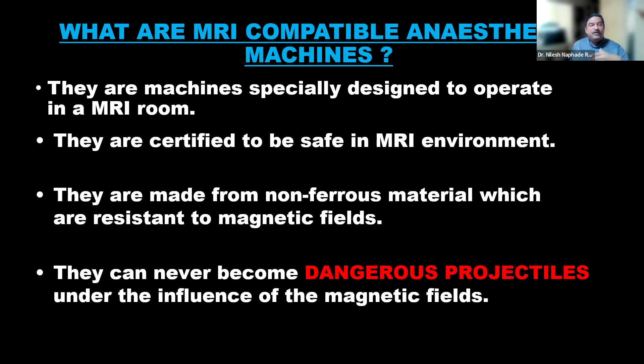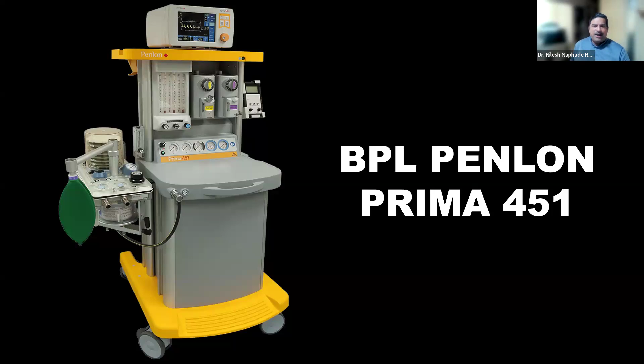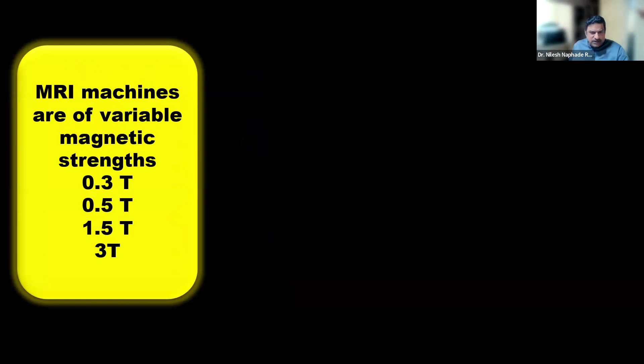This machine which you are seeing on the screen is a BPL Penlon Prima 451. This is a Penlon machine which is sold by BPL in India. Very expensive, but this is a completely non-ferrous machine. And this kind of machine being available in MRI is an absolute luxury. MRI machines are of variable magnetic strengths. You must have heard of 0.3 Tesla, 0.5 Tesla, 1.5 Tesla, and 3 Tesla. There are 7 Tesla machines also, not in India yet. So, as the number grows, the magnetic power of the machine goes on increasing.